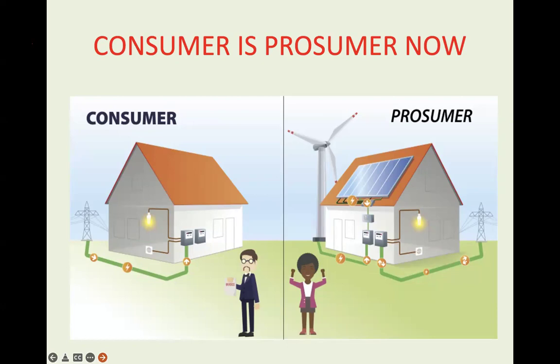When this DC is converted into AC through inverters, these inverters, I'm talking about general inverters, don't generate reactive power. They take care of the active power. Reactive power is still supplied from the utility transformer, and because of that, the core of that utility transformer heats. At the same time, the power factor at your premises becomes low and you start drawing more current to cater the same load that you were catering when there was no rooftop solar. Design it properly and take action properly, so that no such things occur in your system when you install solar PV.